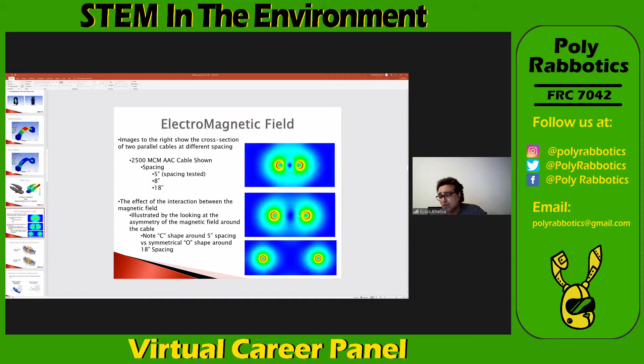You can see if you have two conductors close to each other, how the current will be running. And as you know, the current will run on the outer shell. Since here they are close, you see them pushing each other outside. And here, when you have good distance between each other, you see they are running nicely in a very symmetrical way. So this will also help you a lot when you are designing. That doesn't mean the actual test will be exactly like the simulation, but most of the time it will be good, especially if you do a lot of simulation and a lot of testing, then you know how what you read here is going to convert in real life.